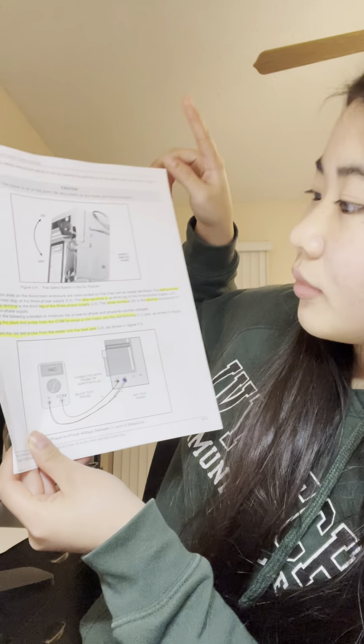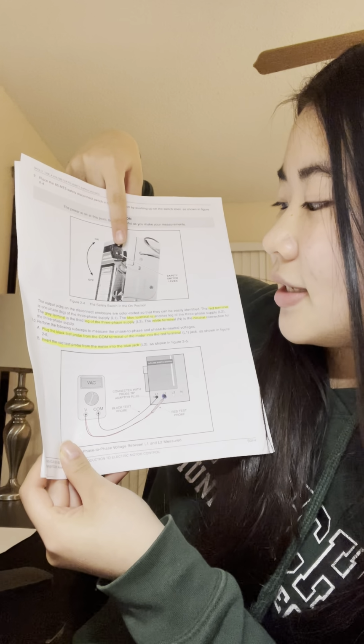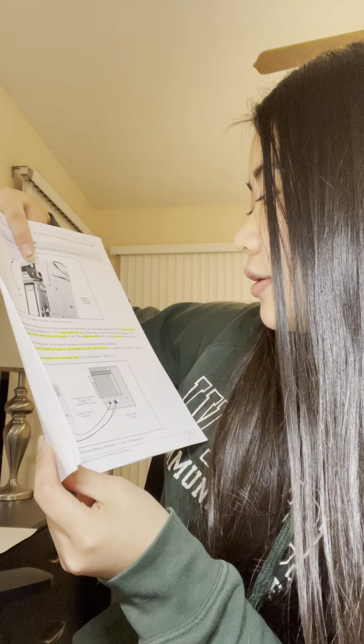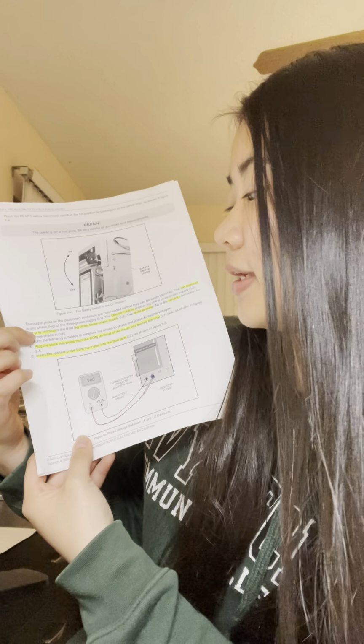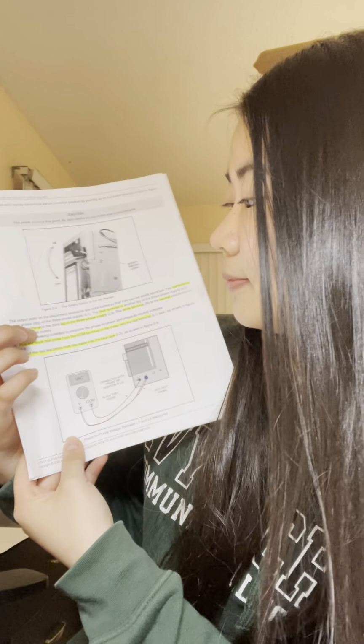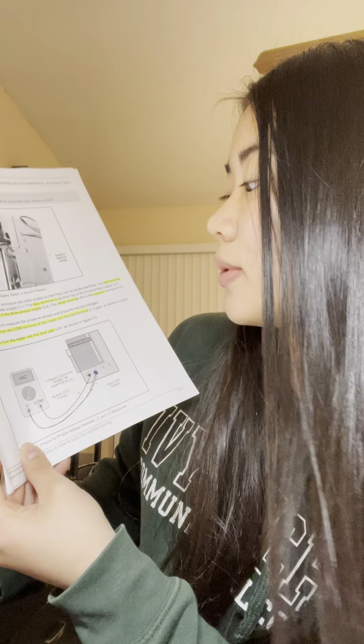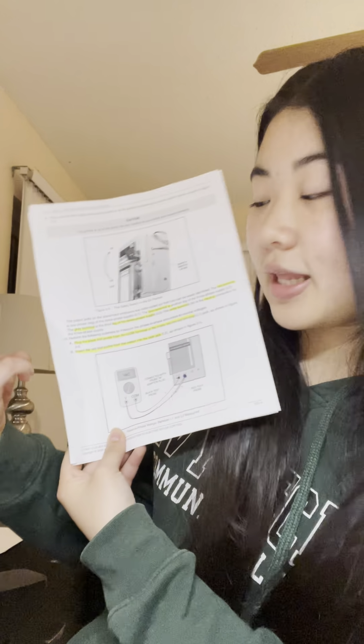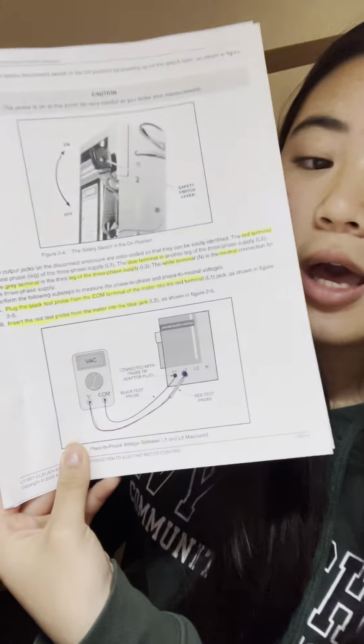The output jacks on the disconnect enclosure are color-coded so they can be easily identified. You know how in 3-phase supplies there are 3 phases? The red terminal is the first phase, labeled L1. The blue terminal is the second phase or leg, it's interchangeable, and labeled L2. The gray terminal is the third leg of the 3-phase supply, labeled L3. So red L1, blue L2, gray L3. The white terminal is the neutral terminal, and this is just called N.